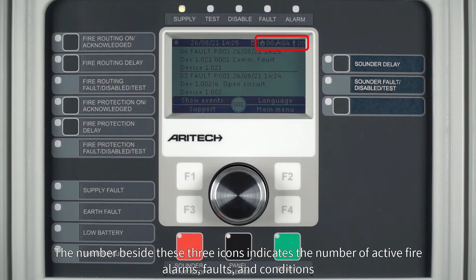The number beside these three icons indicates the number of active fire alarms, faults, and conditions. You don't need to log into the panel menu to check the active events. This means that any user, including a public user without entering a password, can check the active events. As only 2 events can be displayed, you need to go to the Show Events menu to view the others.